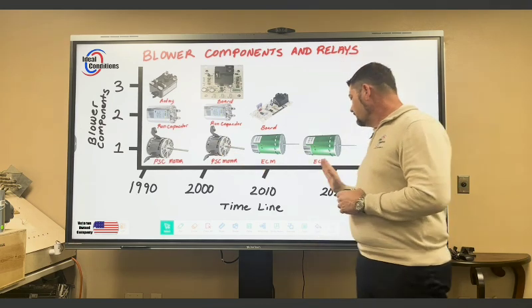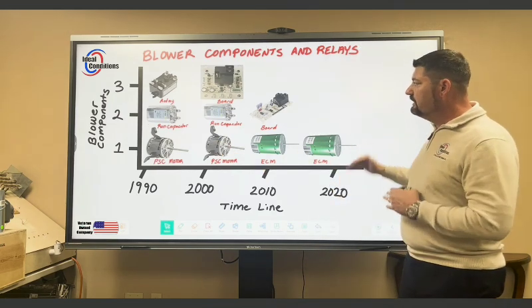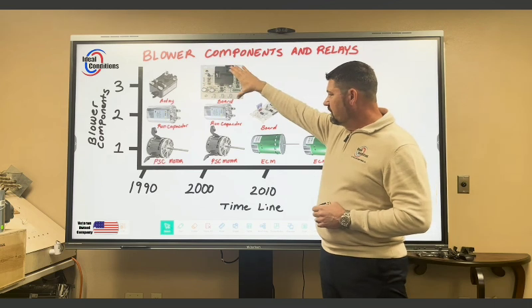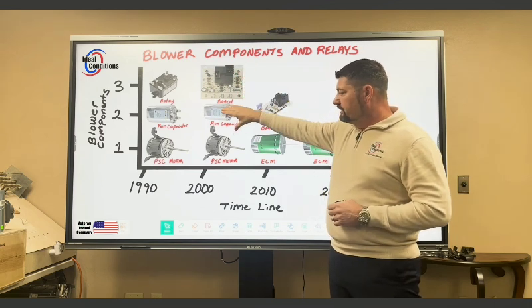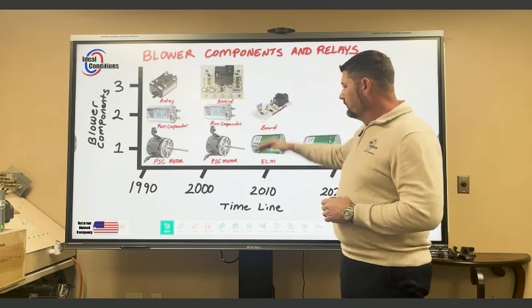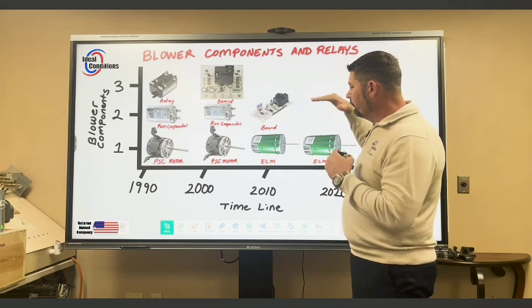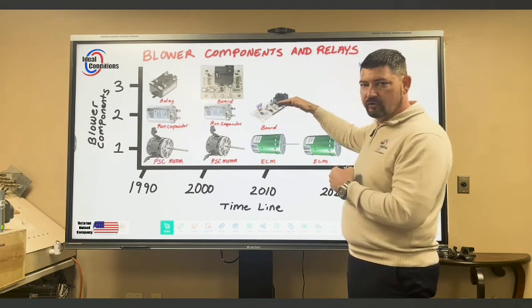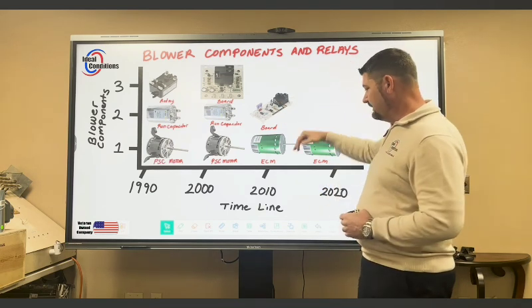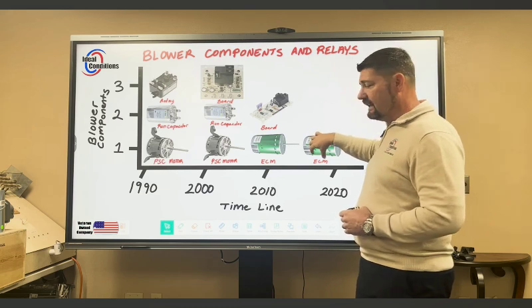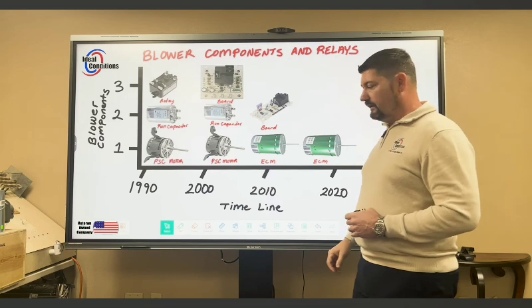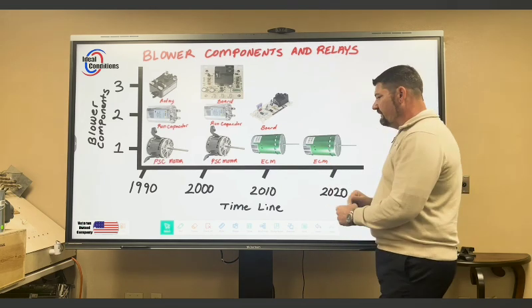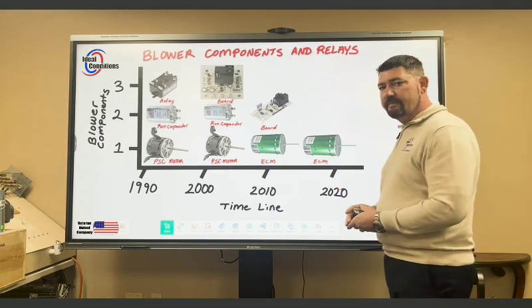By the time we get down to present day, we're losing components. After we're done talking about these boards with run capacitors on PSC motors, there's nothing but ECM modules to go over, with a control board or without a control board. By the time we get here, everything's integrated into the back side of that, which is very proprietary. A lot of times we don't have the availability to just go ahead and put another ECM in there.